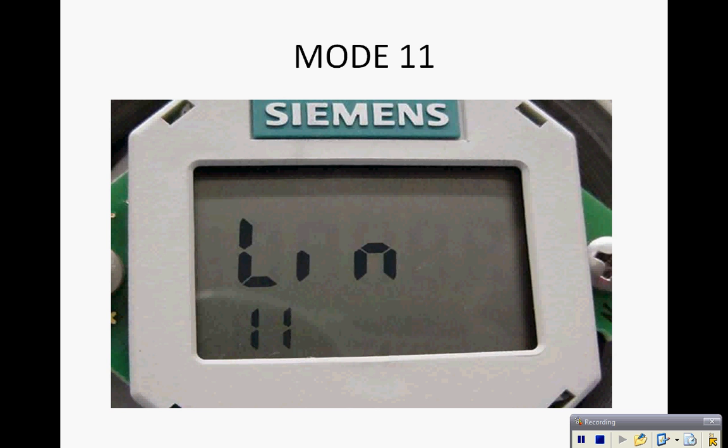Mode 11 as you see here set up in linear, we can also make this transmitter in a square root mode by toggling the push buttons until it reads square root should you have used the transmitter for a flow application.